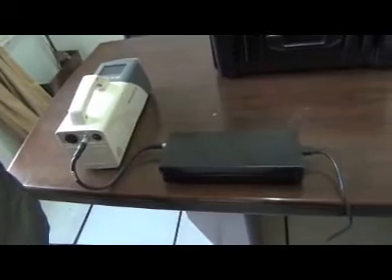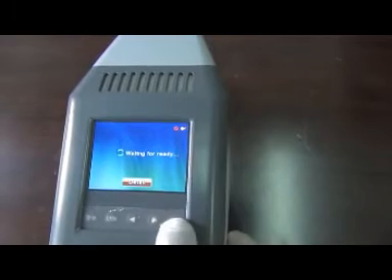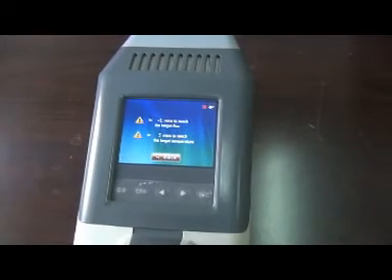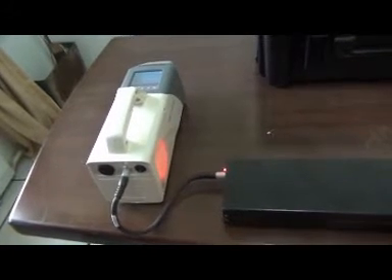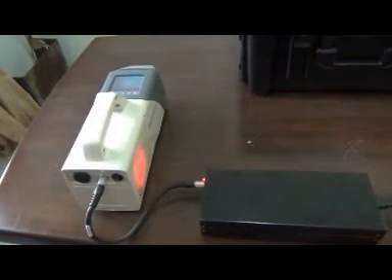Basic operations. Step 1. Starting. Turn on the power of the adapter. Then turn on the power of the device. The starting window is displayed and the system starts self-test. After successful self-test, the waiting for ready window will follow. The operator should turn on the power of the device for 4 hours at least for any device not in use for more than 1 week.